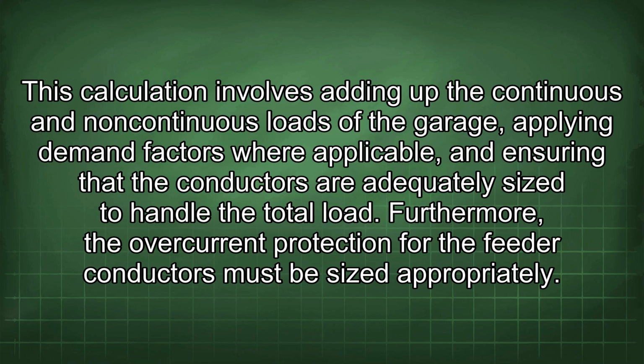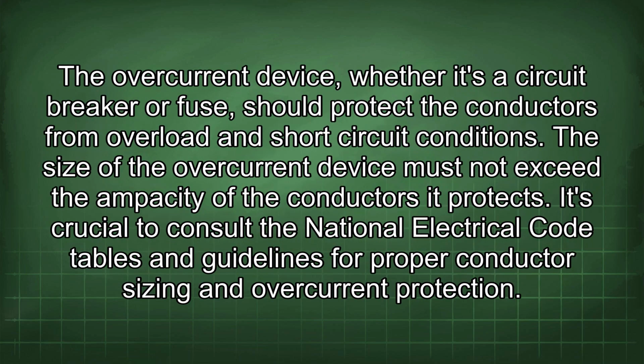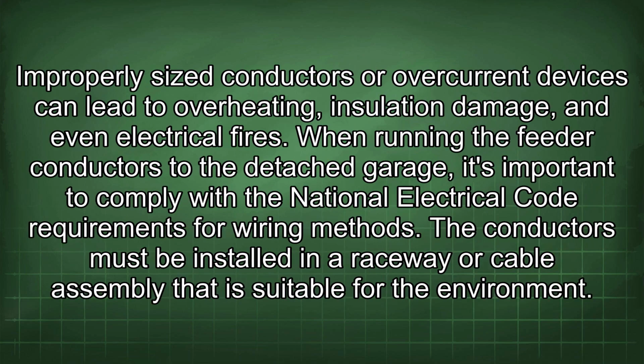Furthermore, the overcurrent protection for the feeder conductors must be sized appropriately. The overcurrent device, whether it's a circuit breaker or fuse, should protect the conductors from overload and short-circuit conditions. The size of the overcurrent device must not exceed the ampacity of the conductors it protects. It's crucial to consult the National Electrical Code tables and guidelines for proper conductor sizing and overcurrent protection. Improperly sized conductors or overcurrent devices can lead to overheating, insulation damage, and even electrical fires.